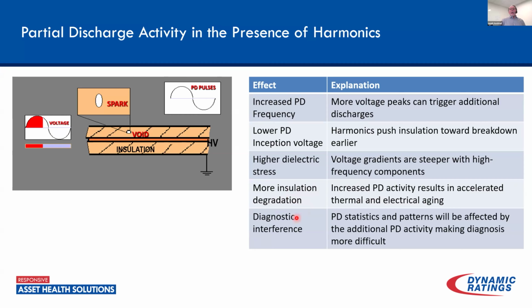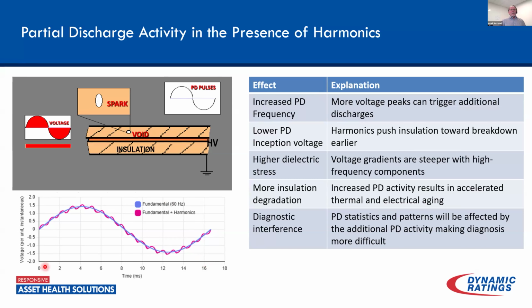The other thing that can happen as we introduce harmonics with partial discharge is that, because I may now have more partial discharges, I could see overlapping patterns and things like that. So the diagnostics could become more difficult. To give you a rough idea of the harmonics we're looking at, take that 17th harmonic that I was looking at before. Here I overlaid what the harmonics would look like on the fundamental. Each oscillation of that harmonic, if it's high enough, could result in partial discharge. So instead of just one partial discharge here and one on the other side of the sine wave, I'm looking at multiple within that same cycle. Again, you can see how this can result in increased partial discharge frequencies.